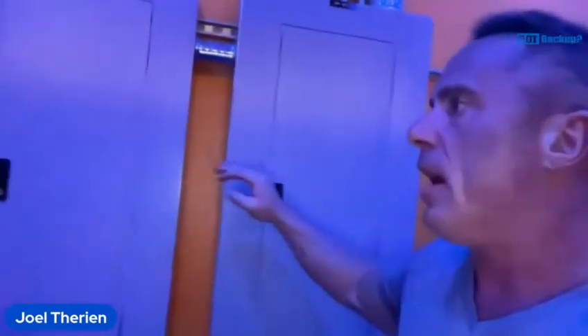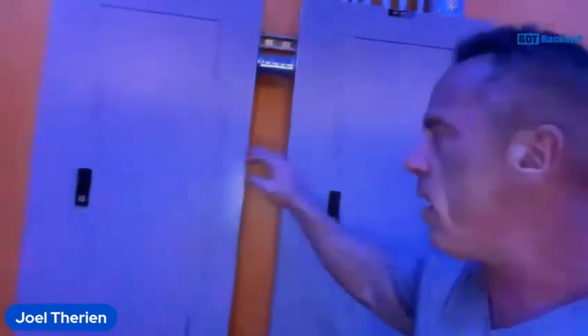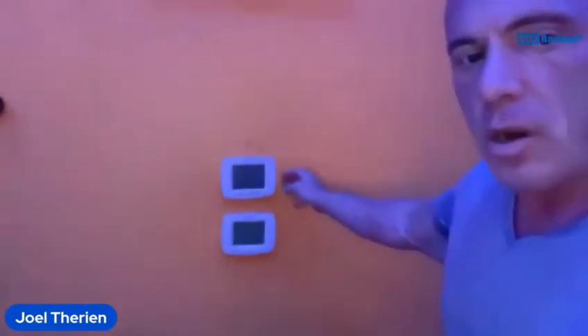Same with the power. A power, B power. Every single server is plugged into A power and B power. If A power burps or goes down, B power takes over, okay? Same thing with the air conditioning. We have 4 air conditioners in this server room.